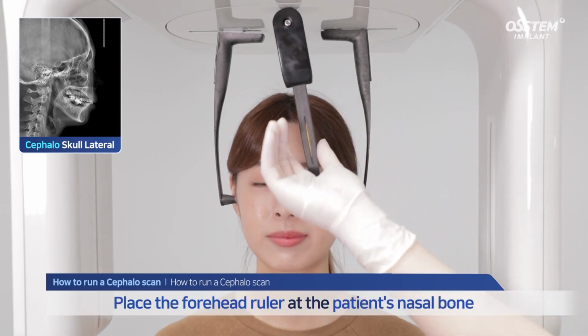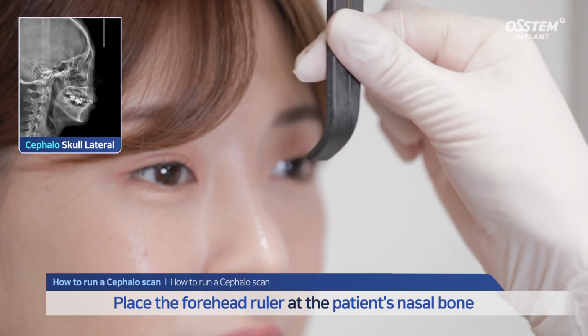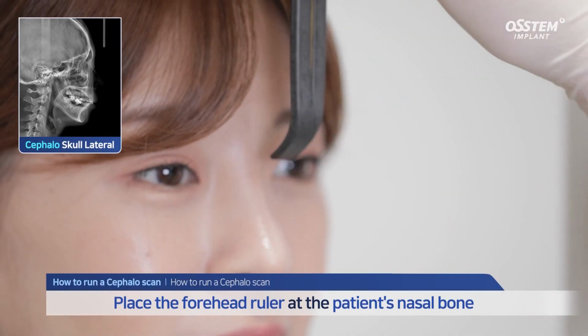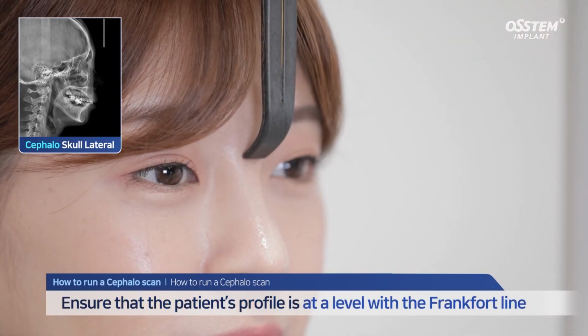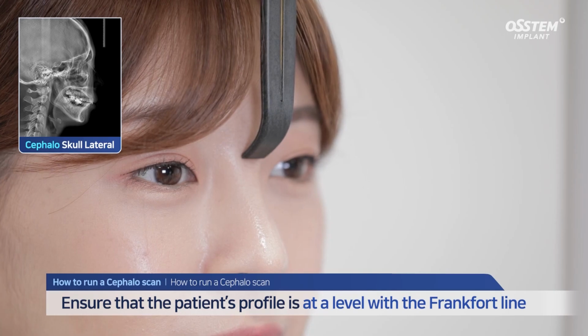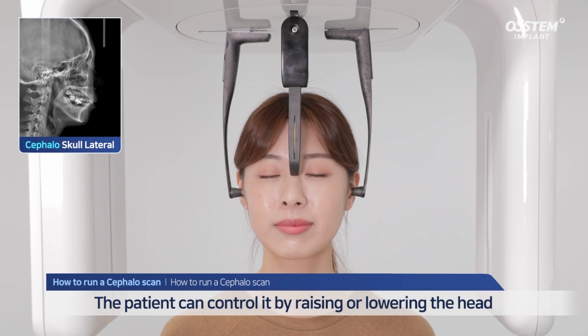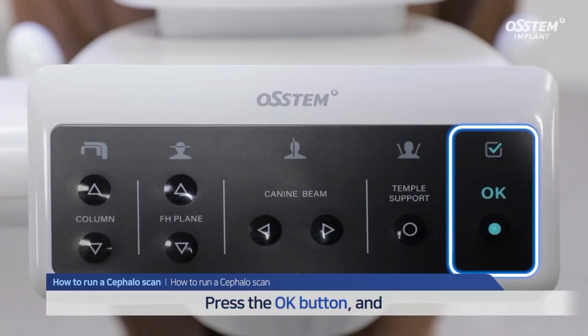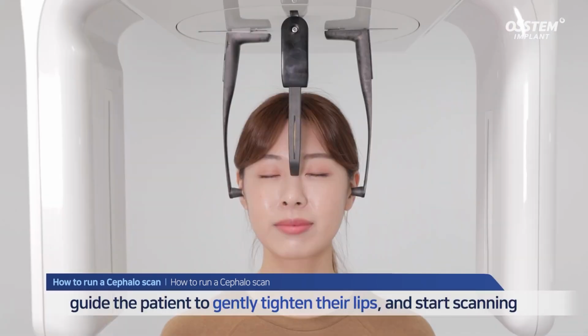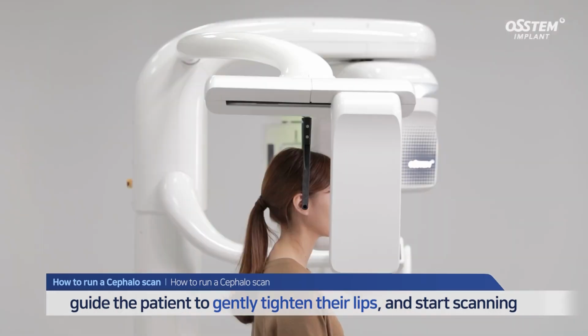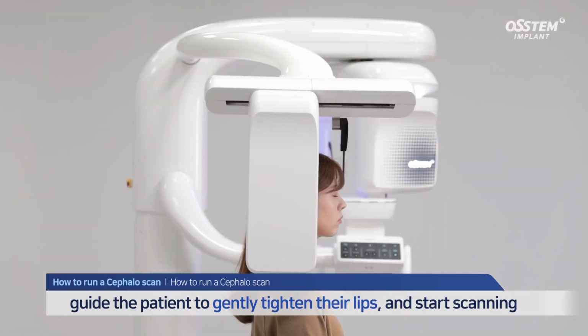Place the forehead ruler at the patient's nasal bone. Ensure that the patient's profile is at a level with the Frankfurt line. You can control it by raising or lowering the head. Press the OK button, instruct the patient to gently tighten their lips, and start scanning.